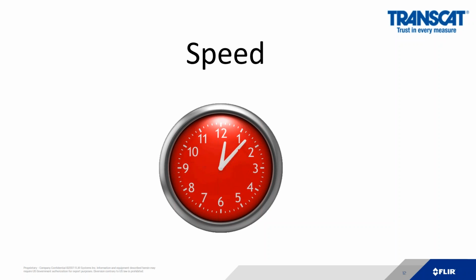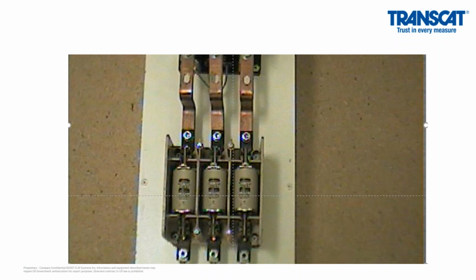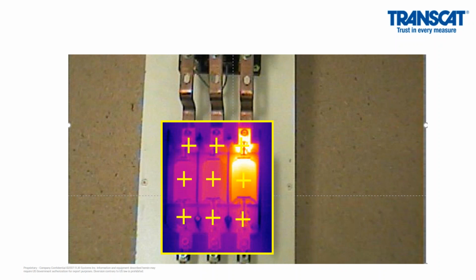The other benefit is speed. How quickly can I find a problem with the thermal imaging camera versus a spot gun? So in this example, if I'm looking at this circuit and I was using a spot gun, I'd have to measure this component a minimum of 9 times. I am looking for the delta between A, B, and C phase across the two connections in the body of the fuses. That equals 9 times. In comparison, a thermal camera only has to look at it once. So if you had to look at 9 different circuits, that's 81 different measurements, with most of the measurements being probably not a problem. There wouldn't be a problem there.